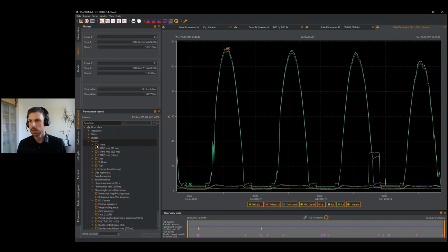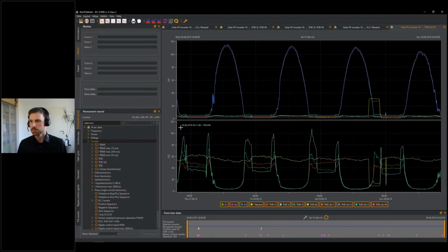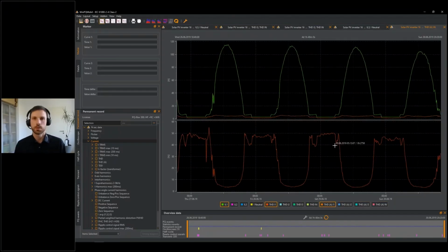So this time I open all 3 values, 1, 2, 3. I will start with the current on top, the THD and the THD in amps. I open a timing diagram and I will just go with phase 1 to see it a bit better. So the THD in percent is very high during the night, but the current that flows is very low during the night. During the day, my THDI is not that bad. It's less than 10%, and the actual current that flows is way higher than 100 amps. So this is something you have to take into consideration when having a look at the total harmonic distortion of currents.